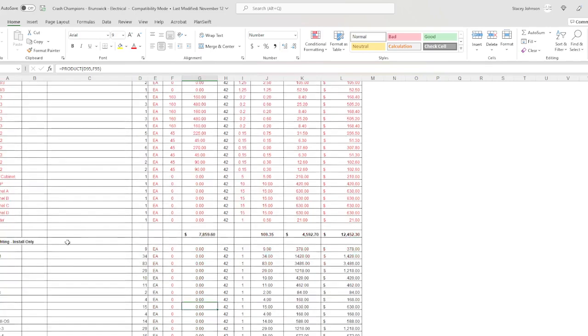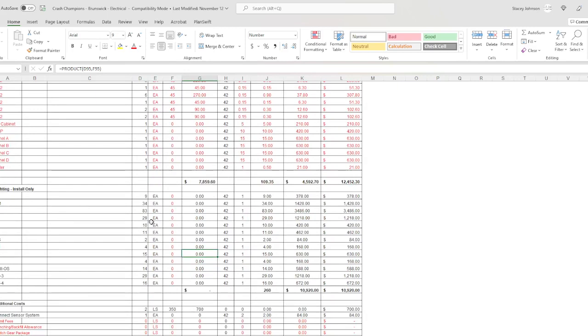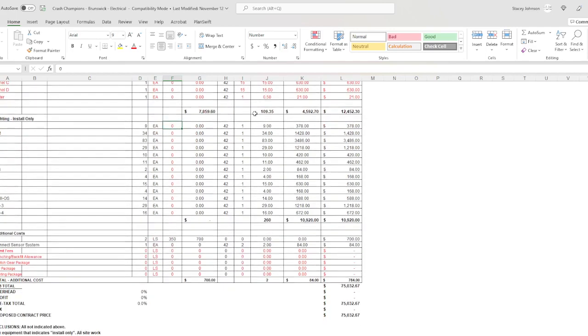All right. And then all of our lights, right? Counting tool, really good counting tool. And again, you're going to get your lighting package depending on the type of, if it's like an Applebee's or Cheesecake Factory, they have a supplier. You call them, they'll give you the material cost for all the lighting package, and you just fill in the blank afterwards. But of course, we give everything an hour for the lighting. And you can be even more detailed than that because most things don't take an hour, unless it's a track light, then we give 0.25 of an hour for that.